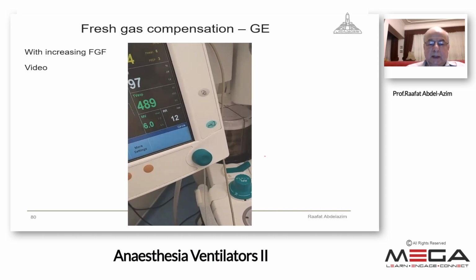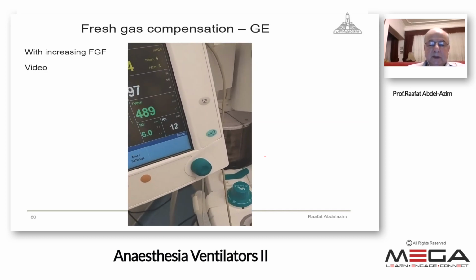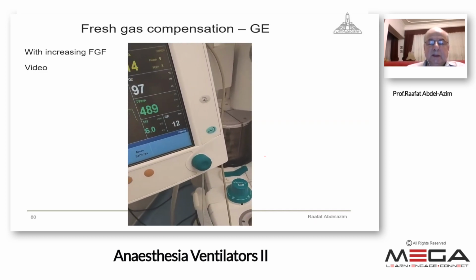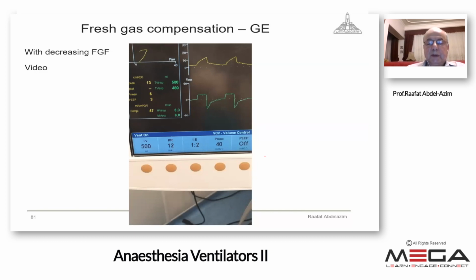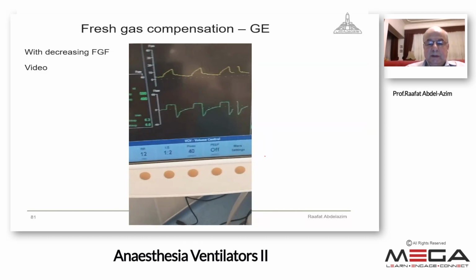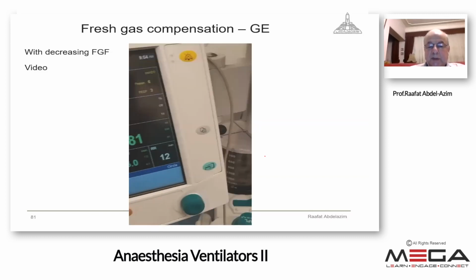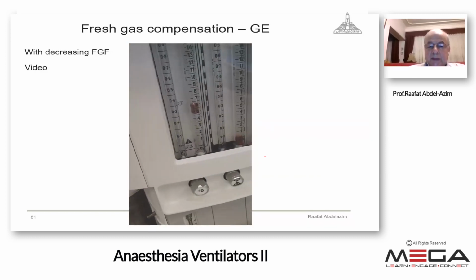I'm doing nothing now. It's only observing. So again, it is near the preset tidal volume as before. The reverse will occur when we decrease the fresh gas flow. You see the delivered here is 480, approximately the 500. The fresh gas flow is 6 liters.